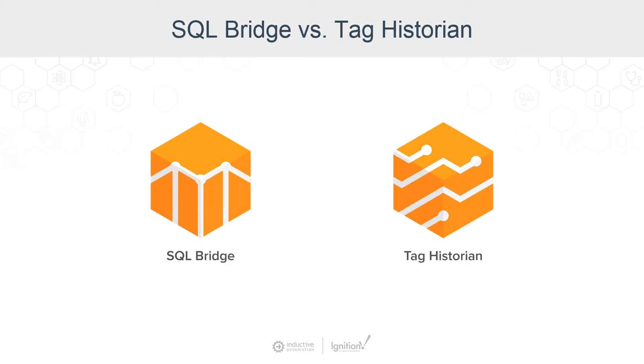The Tag Historian module was created primarily for trending of your process values. It is an easy way to log your tags into a SQL database, and then simply view a graph or summarize it in a table form to bring it back. We've done a lot of work to keep that very efficient and easy to configure, especially when using SQL databases, since a lot of our customers don't know much about databases.